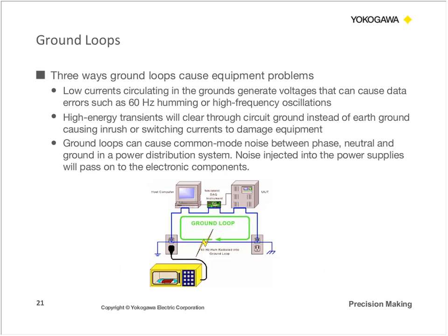The second problem that it can cause is high energy transients. We talked about the case where the lightning strike causes the ground potential to jump up several hundred or several thousand volts, and these transients will want to clear through the circuit ground instead of the earth ground. So what's going to end up happening is it's going to run through your instrument and your device as opposed to running through the receptacle or the earth ground, which you would expect, but in this case, it's going to damage your equipment.